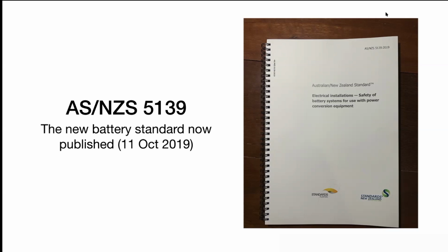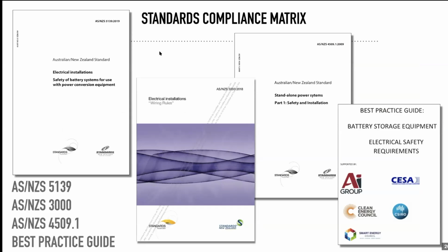So let me just move forward on this one and show you the collection of standards that you need to consider. So here we've got 4 documents on the screen, and they really are the 4 documents that you need to consider when installing a solar and battery system. The battery standard 5139, the scope of that we'll cover in a second, but basically it covers everything after the inverter or charge controller, all of the DC side of a battery system. And if it's an integrated solution, such as a device that has an inverter built into the battery module, then it covers that as well.